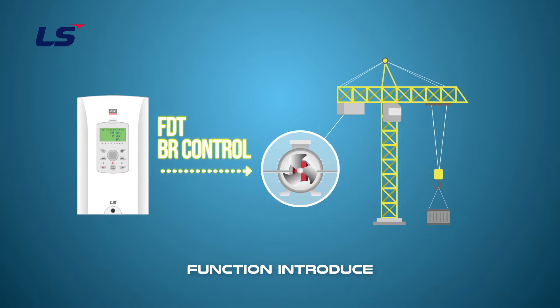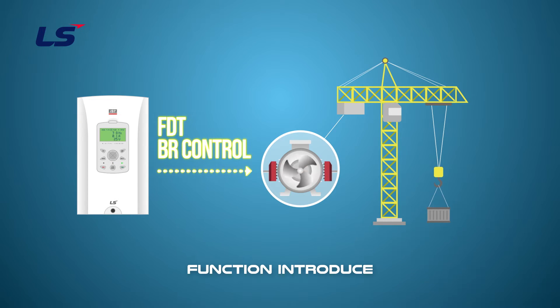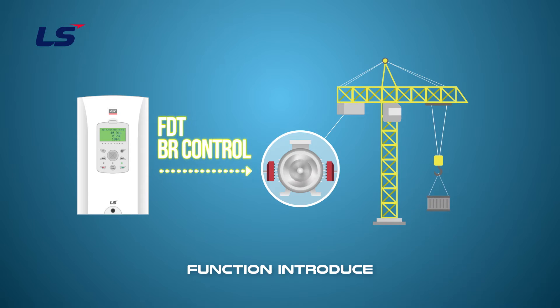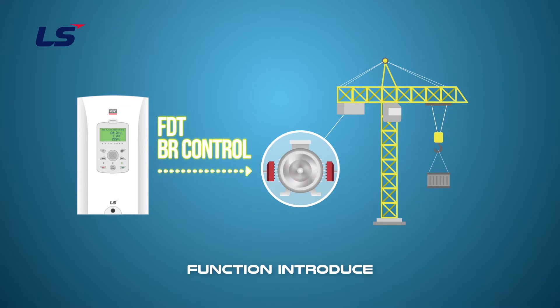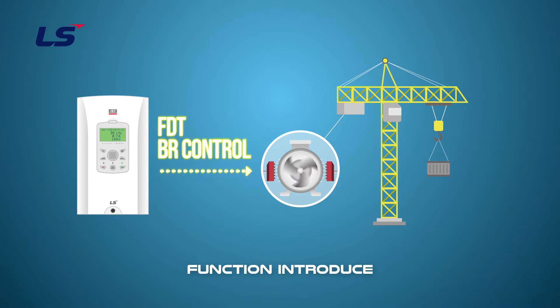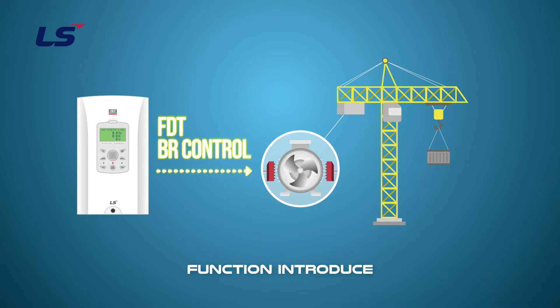The brake opening signal from the drive goes out through a terminal output signal. The operation voltage of the brake is applied through the control panel and the brake opens. Then the brake is closed when the signal from the drive is removed.